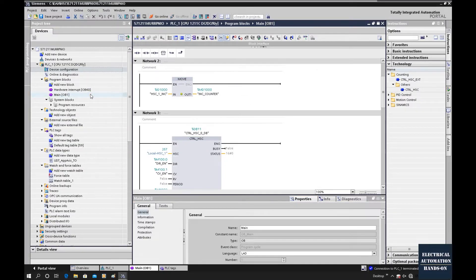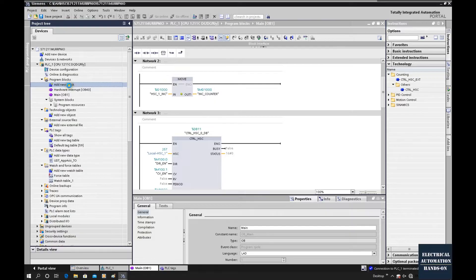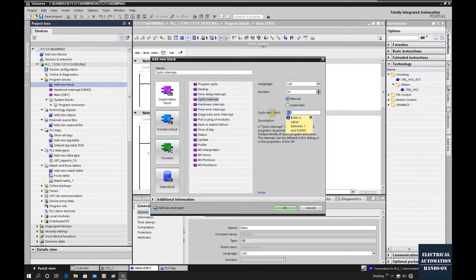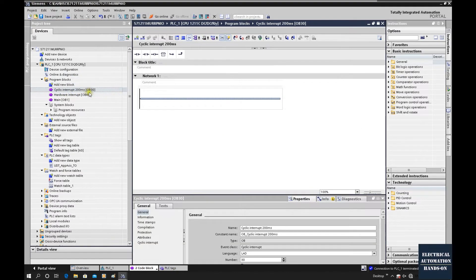To accurately count the speed, a one-second unit is not enough — we need to sample the counter a bit faster. We will use the cyclic interrupt. Let's add a new block: pick 'Organization Block' and select 'Cyclic Interrupt'. We can use 200 milliseconds as the cycle time and name it 'Cyclic Interrupt 200ms'. Once downloaded, OB30 will automatically be called every 200 milliseconds — that's why it's named cyclic interrupt.